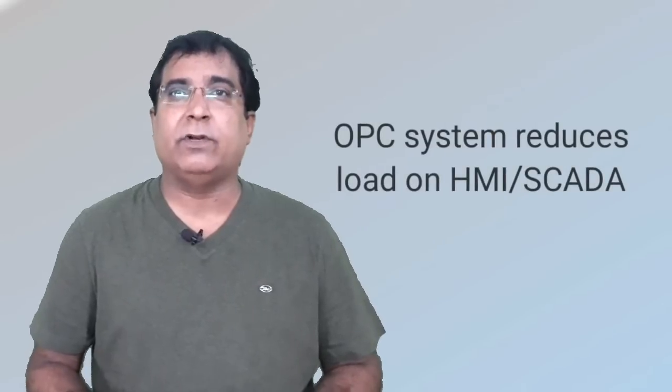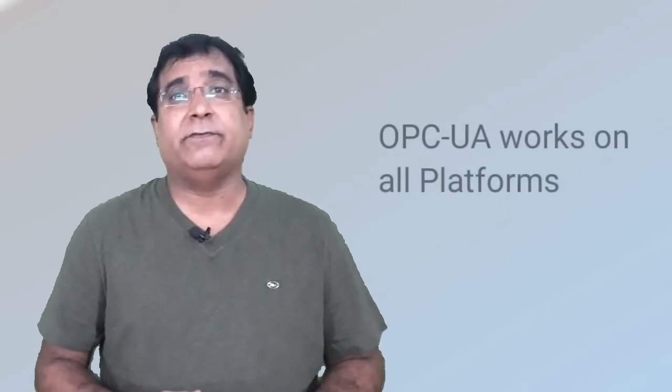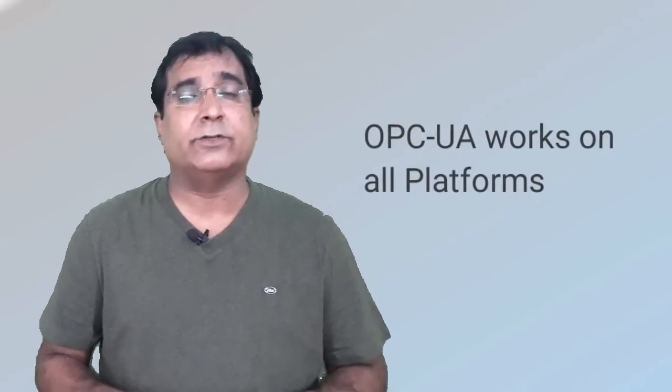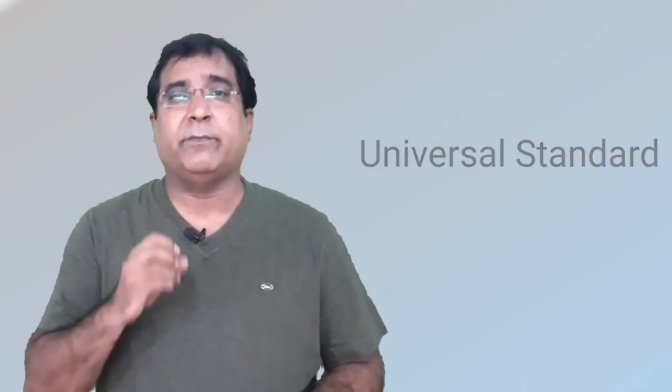Let's check out the benefits while using OPC. It omits all kinds of drivers with the PLC hardware or control system hardware, so basically it reduces the load on the SCADA and HMI application. Only a single OPC Server can communicate with different PLCs. Second one: SCADA HMI applications do not need to know communication details of different hardware protocols. It can communicate with any hardware absolutely. Third one is interoperability with various OS like Linux, Windows, Unix. It is open for all systems. And third is total standardization. Any make of OPC Client can communicate with any make of OPC Server. That is the beauty of this OPC standard.